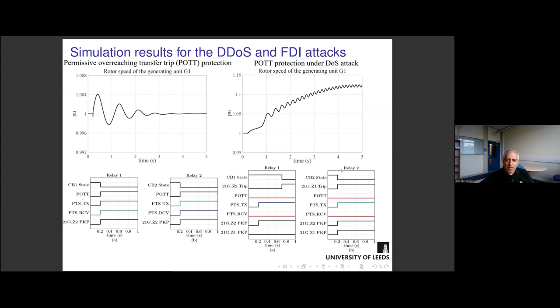On the right-hand side, we can see the DDoS and FDI attack results. As we can see, again, the fault has happened at 0.2 seconds, but in this scenario, because the communication channel between the two substations has been under attack due to distributed denial of service attack or FDI attack, it couldn't communicate with the remote substation. Therefore, the fault remained on the transmission line beyond the critical fault clearing time. And because of that, the generator lost synchronism. And because of that, the 4 generating units that we had in this benchmark test system disconnected from the system. And if an attack like this happens in the real world, it will become a huge disturbance in the power system and can easily become a blackout in the system and force the whole system to go to a blackout.